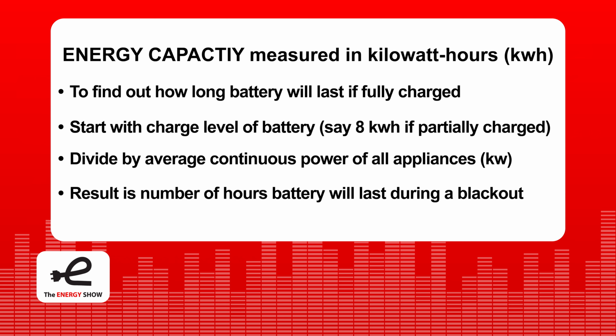Also keep in mind your battery is not always going to be fully charged. In reality, many people cycle their battery fully from 100% down to like 20 or 30% at night. If your battery's at 30% or 50% at night—let's say there was a power failure at midnight and your battery was at 50%—the battery's only going to last for 0.9 hours if you're trying to run these big appliances.